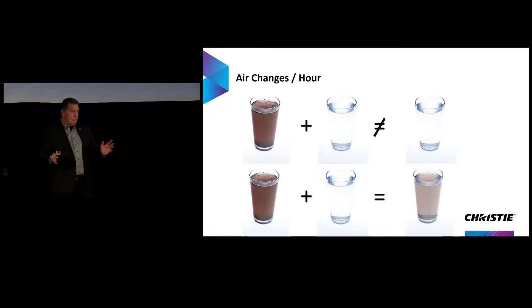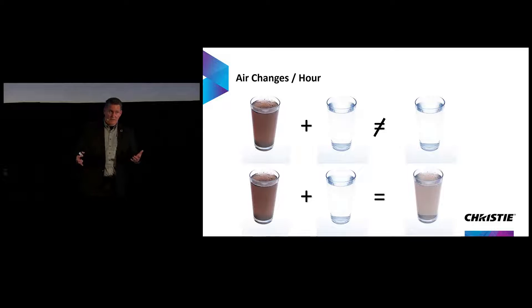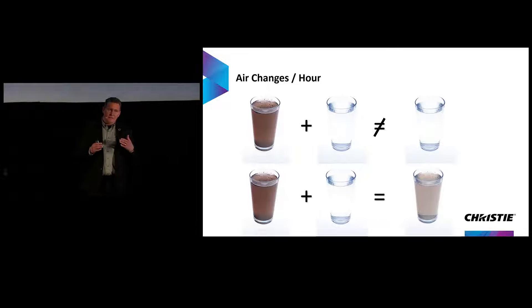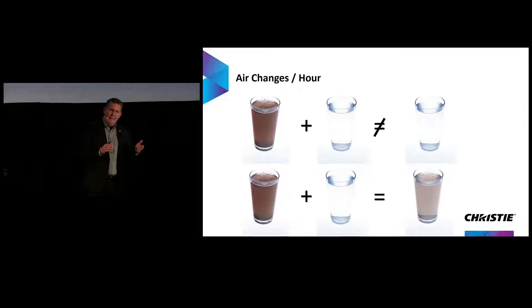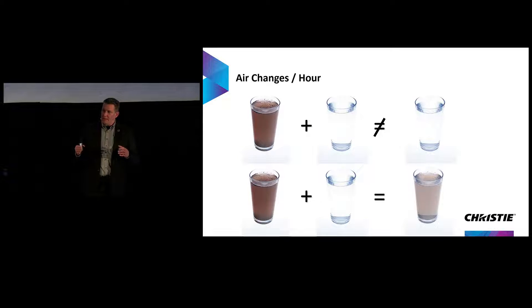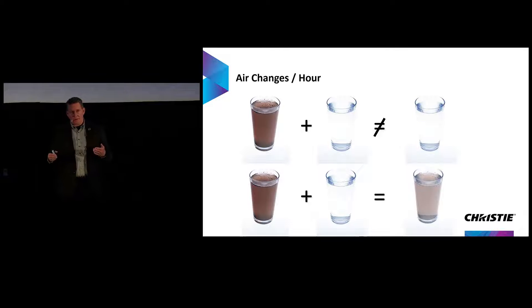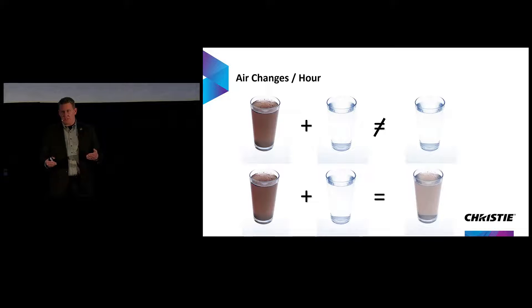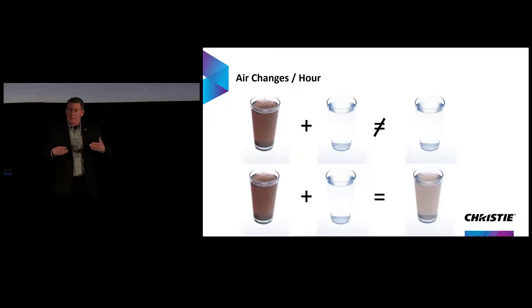You may be thinking: if I can do ten air changes per hour like a hospital, I can reduce concentration to 6.5%, and that's got to be good. But the challenge is that that's from your initial starting concentration — that's like saying the sick person left the room and an hour later I have it down to 6.5%. This is why it's not enough to just look at air changes per hour. We need pathogen inactivation systems in our buildings that combat pathogens at a very high rate, because if we're going to interfere with future pandemics and the flu moving between people, it's important that it's done while people are in the room, not just after they've left.